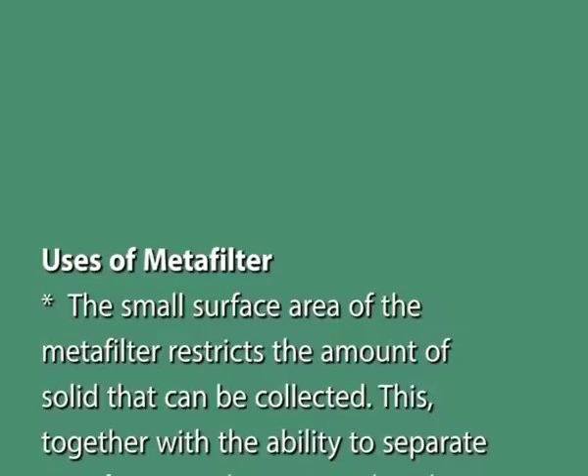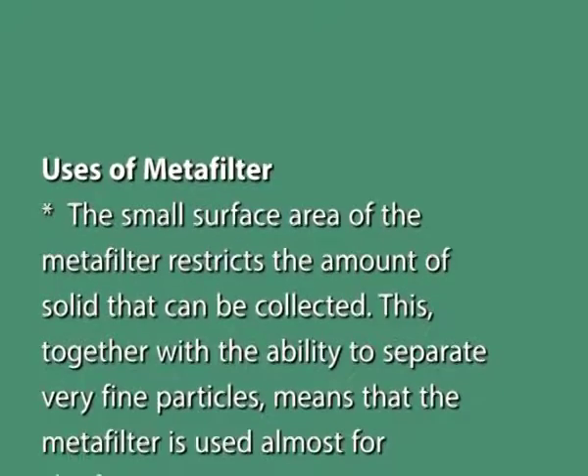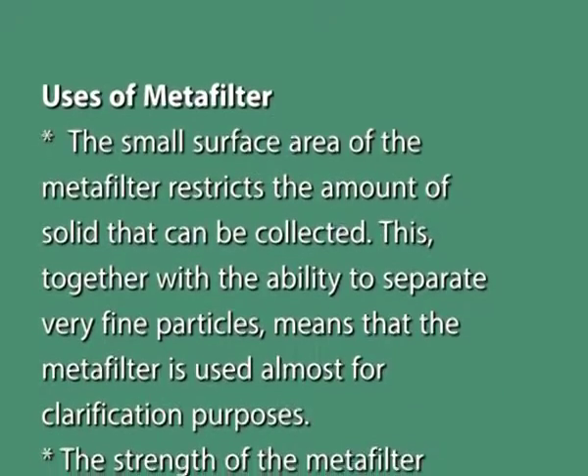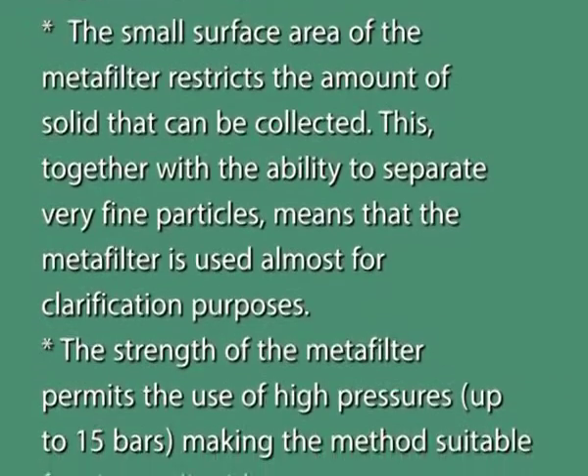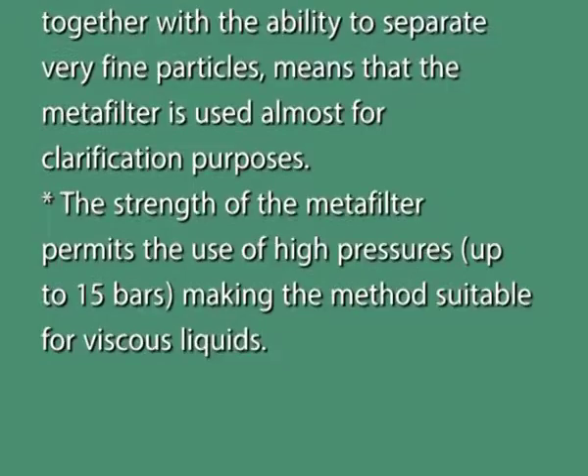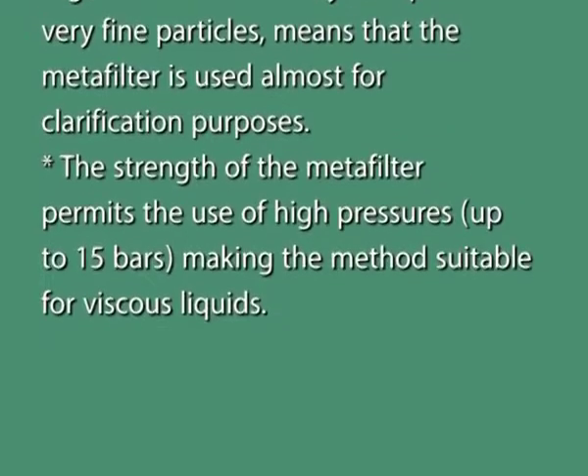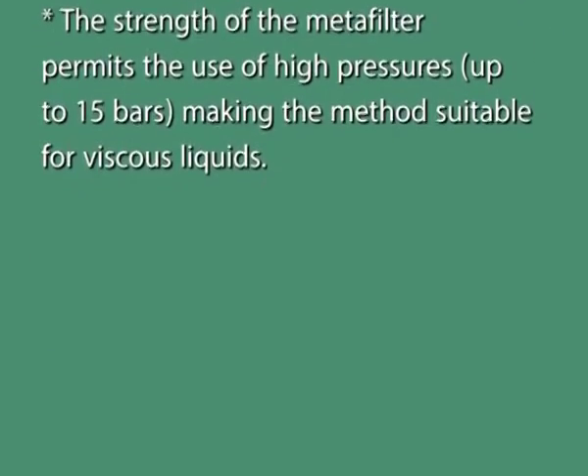The small surface area of the Metafilter restricts the amount of solid that can be collected. This, together with the ability to separate very fine particles, means that the Metafilter is used almost exclusively for clarification purposes. The strength of the Metafilter permits the use of high pressures up to 15 bars, making the method suitable for viscous liquids also.